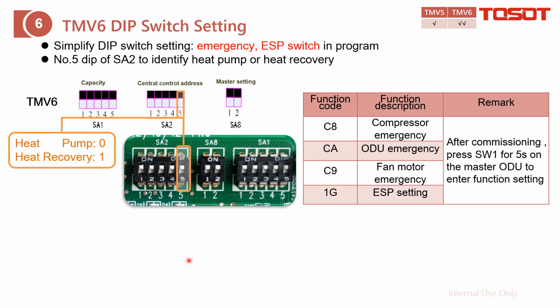GMV6 dip switch setting. This topic is very easy because there are only 3 dip switches at the outdoor unit PCB. We have put the emergency, including the compressor, the whole outdoor unit, the fan motor, and also the components, into the program. Besides, we also put the ESP into the program. You need to use the switch to select the function to turn it on and also to select which ESP you would like to apply. And let's go back to this switch. You can find it, there are only 3.